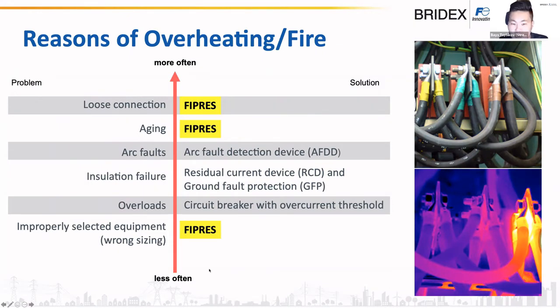As you can observe from the list, there are some standardized solutions which are mandatory to use, like AFDD or RCD or GFP, and because they are standardized, you can easily find them in every single electrical panel. Let's say the circuit breaker with overcurrent threshold, you can find in any panel. But when it comes to loose connection or aging, there is no such standardized solution. Even though it's a very common problem, and it's really a problem, there is no standardized solution, as I said before.